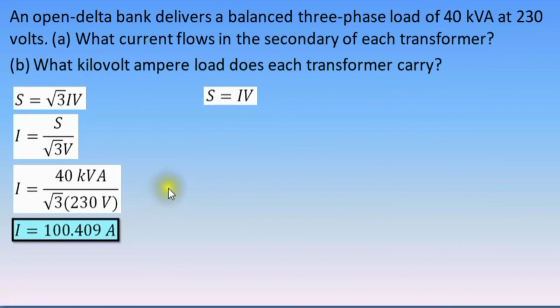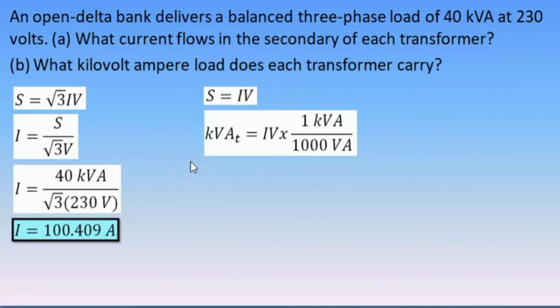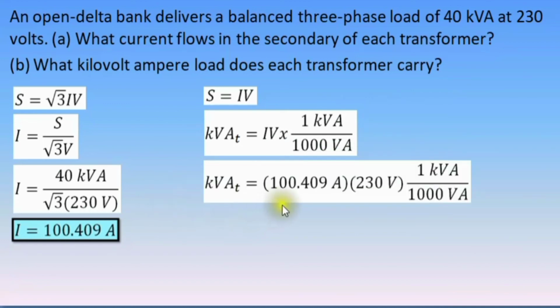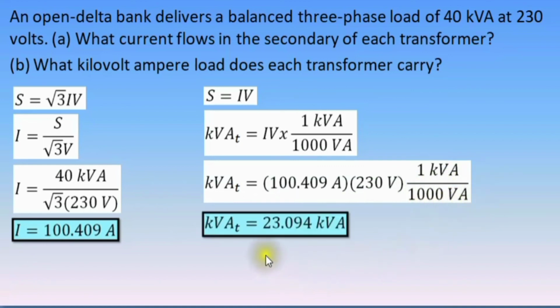For letter B, kilovolt ampere load of each transformer. Again, since we are solving for the kVA load of each transformer, we use this formula. But since we are asked to determine its kVA load, we multiply that by 1 kVA divided by 1000 volt amperes. Substitute the values. Current equals 100.409 amperes and the voltage is 230 volts. Multiply that by 1 kVA, divide that by 1000 volt amperes. The answer is 23.094 kVA.